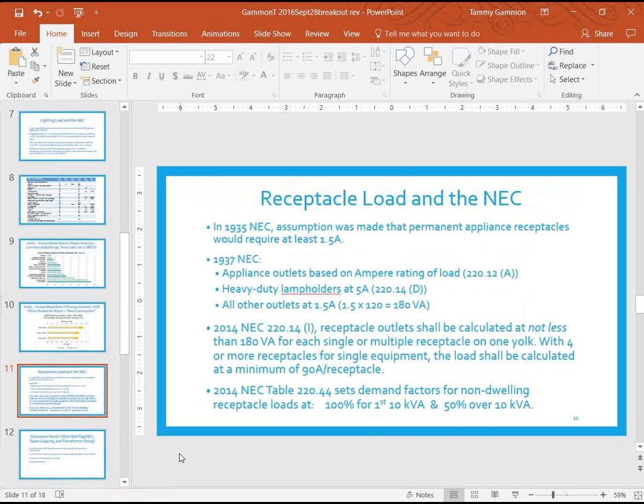So anyway, if we can go on to the receptacle load: in 1935, the assumption was made that permanent appliance receptacles would require at least 1.5 amps. In 1937, the NEC said appliance outlets would be based on the ampere rating of the load. The reason you see 220.12a in parentheses is that's at least the 2014 edition, and heavy-duty lamp holders at 5 amps is still 220.14d, with all other outlets at 1.5 amps, corresponding to 180 VA.